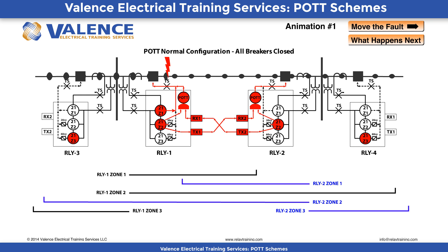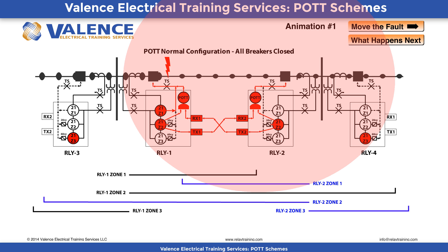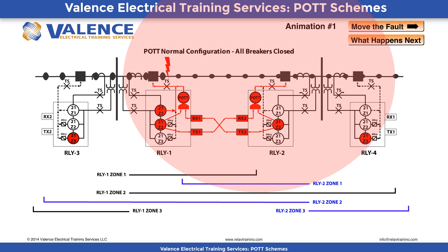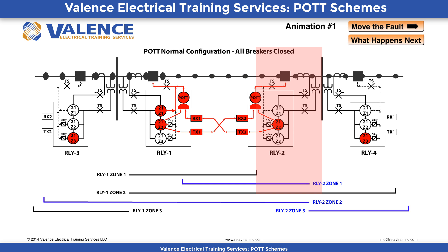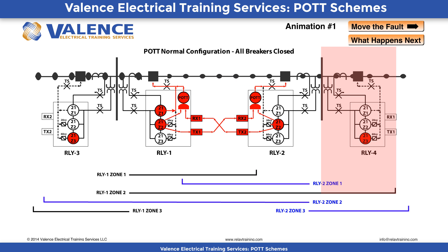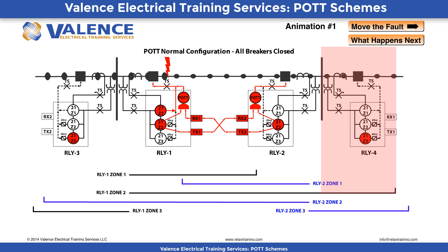We call Zone 2 an overreaching condition because it is purposely set somewhere around 120% of the line as described in the previous videos. Zone 2 is purposely set to detect faults in the section between the Zone 1 limit and the rest of the line, and it provides backup protection for faults on other lines in the forward direction. This means that Zone 2 will detect faults that may not be on the transmission line this relay is installed to protect.